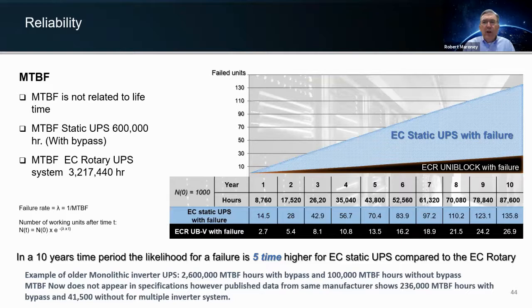Reliability: if you look at the Piller rotary UPS, the ECR, electrically connected rotary UPS uniblock, has a substantially higher reliability rate. This is based on real-time events over the life of the UPS, because Piller does almost all the work on all of our UPS, with over 3 million hours of MTBF. If you look at traditional static UPS today, as they've gone to multi-module systems to achieve power, instead of having one inverter section for a 750 kilowatt UPS, you might have 2 for that size. Or if you're going to a 1,000 kilowatt system, you might have 3 or 4 inverters. Their MTBF has compressed and come down over the years, making the systems have a higher failure rate compared to a single module rotary system.